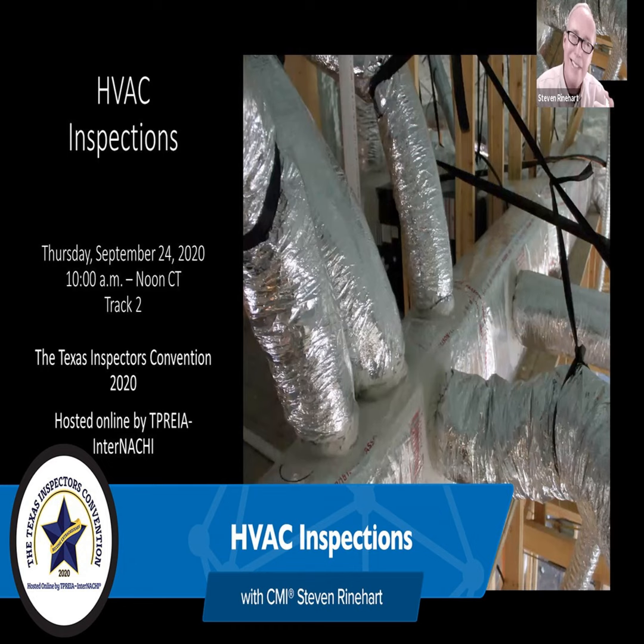It has too many problems, and you also have a health hazard. Think about this. What's in the sewer pipe? Bacteria. Go up on a roof, look down a vent pipe. If the house is very old, you're going to see stuff growing. It's a science experiment. Now you're connecting a hard line of condensation with no air gap, and that bacteria will start growing backwards in your primary condensation drain into your air handler. Do you want that in your air handler? No, I'm voting no.